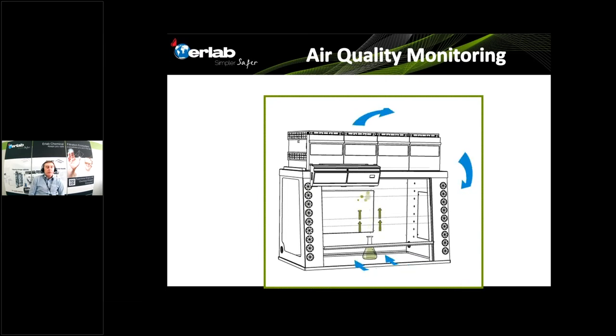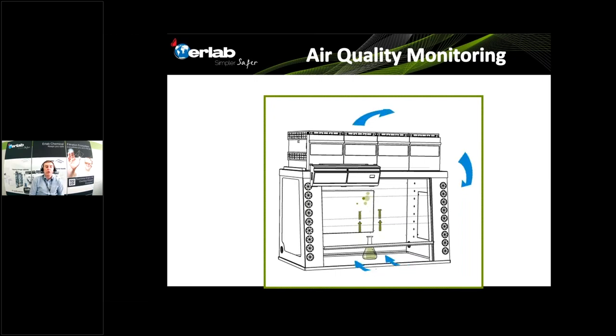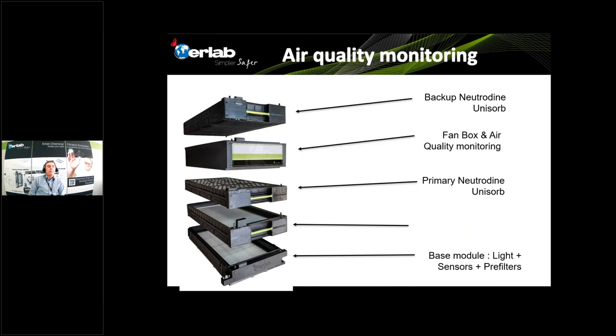We pay great attention to containment and filtration, but filter monitoring and air quality monitoring are also very important. There is nothing in the filter itself that tells you whether chemicals are exhausted from the fume hood. When you use a green fume hood, it embeds sensors that guarantee all the air recycled into the room is free of pollution. These sensors are located between a primary Neutrodine Unisorb filter and a backup Neutrodine Unisorb filter, so that if the detector senses pollution after the primary filter, the backup filter is still there to prevent any leakage into the room.